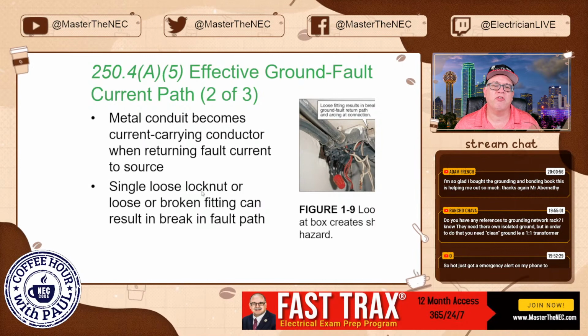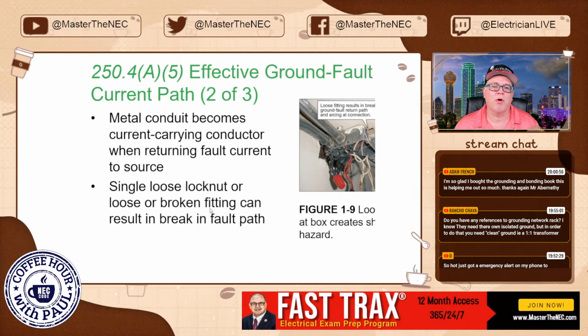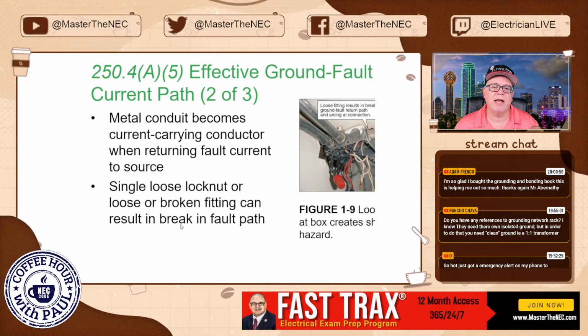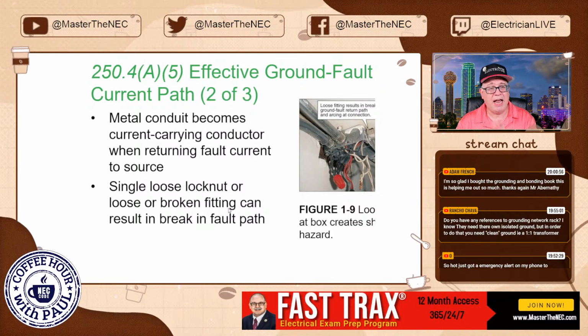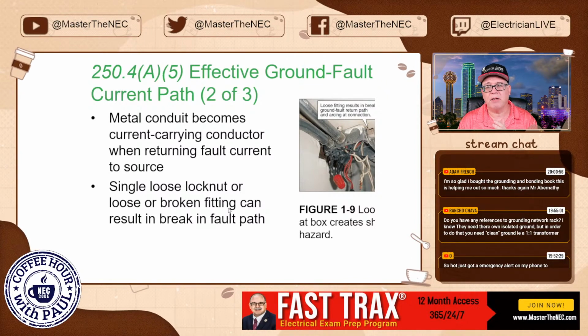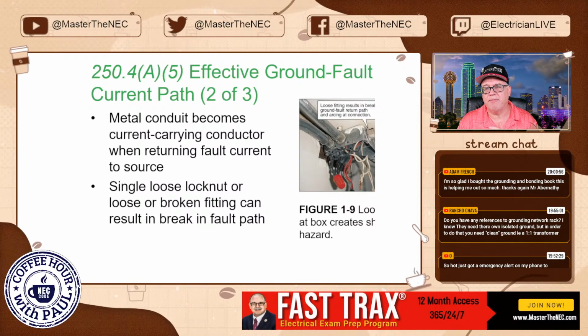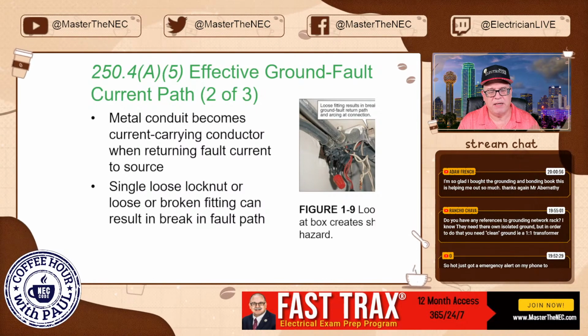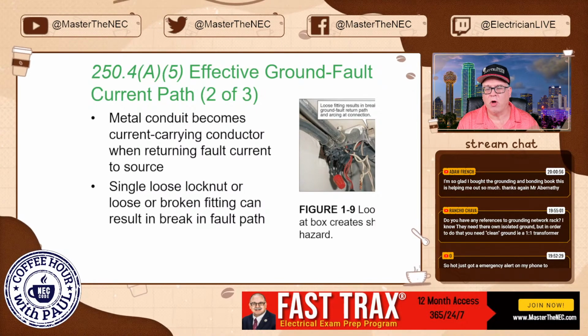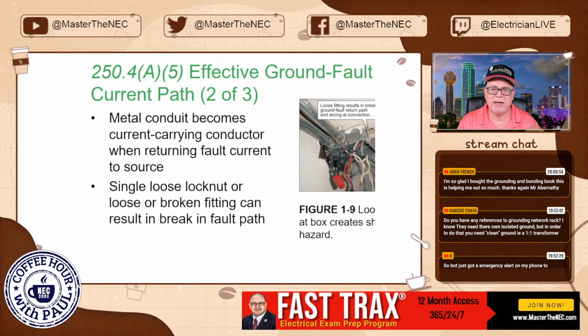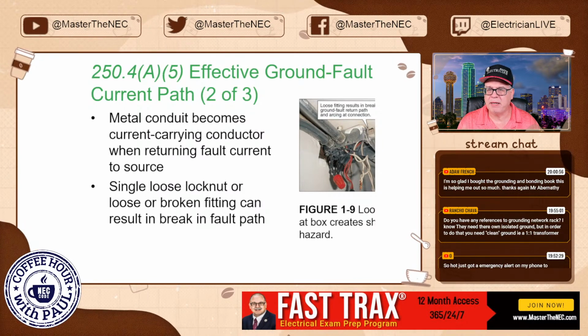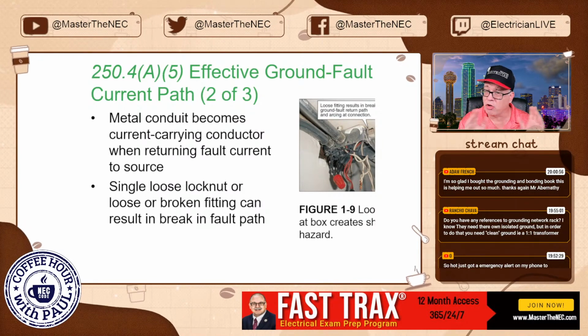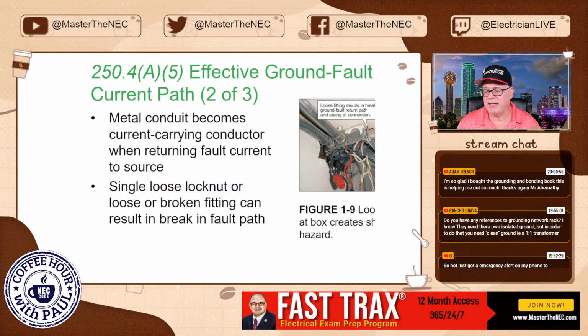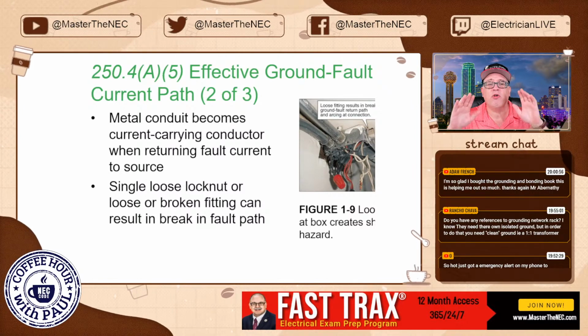A single loose lock nut or loose or broken fitting can result in a break in fault current. Absolutely. I'm going to tell you right now, fittings, die cast fittings. If you don't put some things in with care and pay attention to what you're doing, they can be the weak link. And again, remember, everything's going to work fine until something happens to that fitting. And then it just sits there waiting.